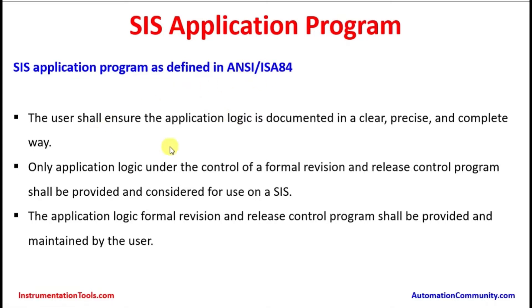The user shall ensure the application logic is documented in a clear, precise, and complete way. Only application logic under the control of a formal revision and release control program shall be provided and considered for use on a safety instrumented system. The application logic formal revision and release control program shall be provided and maintained by the user. There could be requirements for small changes or sometimes major changes due to project implementation.